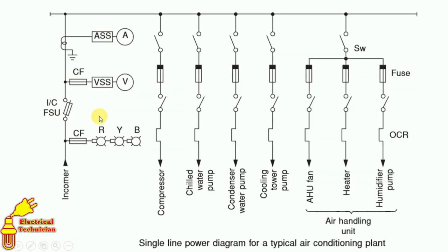Now see, this electrical equipment here, to measure current in these, here one CT is connected. This symbol is of CT. In CT, there are two terminals, S1 and S2. Here is S1 terminal and here is S2 terminal. S2 terminal is earthed and S1 terminal is connected with ammeter selector switch. ASS means ammeter selector switch.